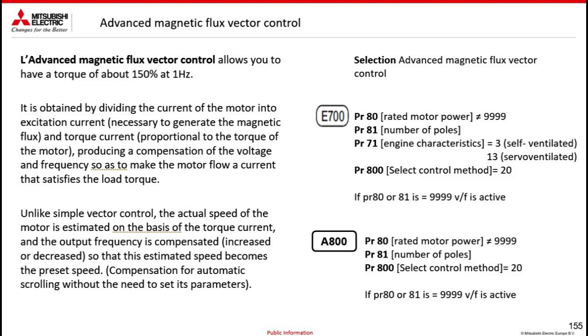If I put the value 11, it means that I want to perform a general purpose magnetic flux vector control auto-tuning. If I indicate the value 1, it means that I am going to perform an advanced magnetic flux vector control. If I want to define the value 101, I want to perform a dynamic advanced magnetic flux vector control, so not static.